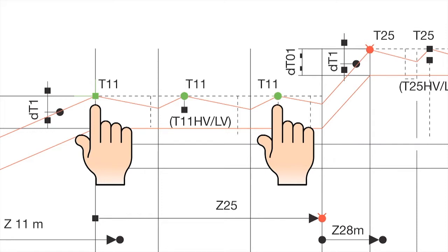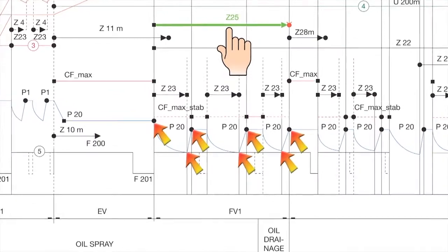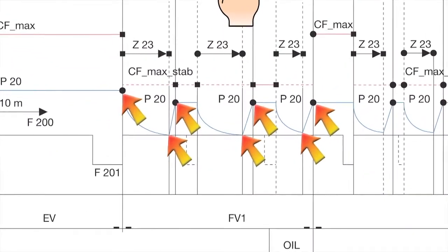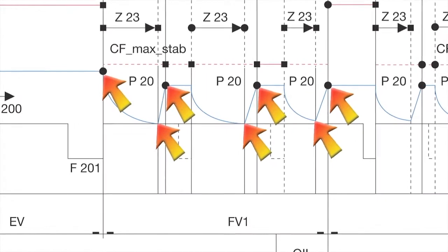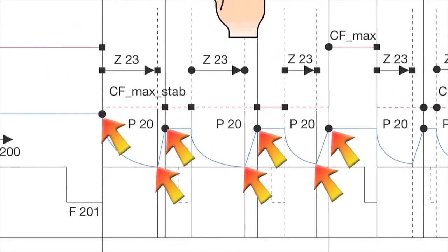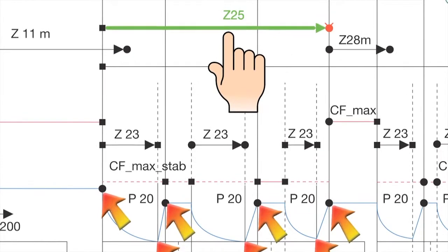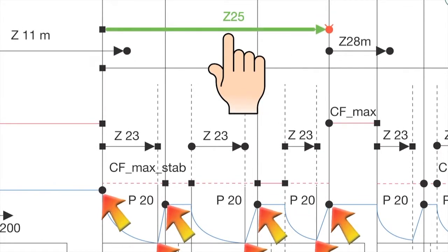After reaching T11 and the temperature for the HV winding has been brought near the average temperature, the process will be switched on to the fine vacuum 1. When oil circulation is selected, the oil should be drained out of the transformer during this process step. Overview. Fine vacuum 1. In order to guarantee optimized drying results, the winding temperature will be intermittently heated with LFH current during a certain period of the whole fine vacuum 1 time, Z25. This assures a better drying quality and reduces the overall drying time.